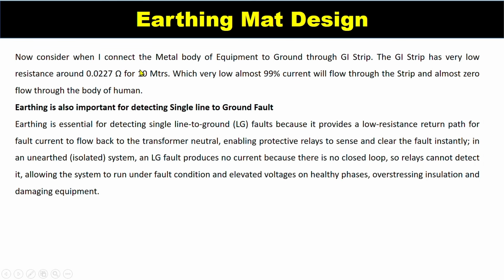Now consider when I connect the metal body of the equipment to the ground through a strip. For our example, we have taken the transformer, and we connect its metal body to the ground through a metal strip. The GI strip has very low resistance, around 0.0227 ohm for 10 meters, which is very low. Almost 99% of the current flows through the strip and almost zero current flows through the body of the human.